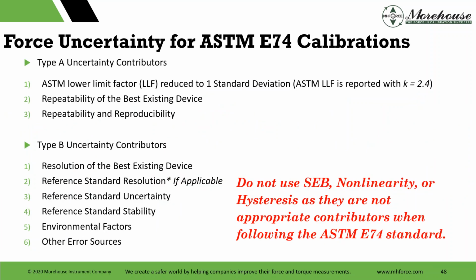Anyway, going on, we had that paper on uncertainty, and typically when we're looking at uncertainty for force, it doesn't end with what I just showed you of the 0.002. You have to get that device, you're accredited, and now you have to do more. And this is the more that most people do. You're going to take your type A, which is going to be the ASTM lower limit factor, reduced to 1 standard deviation. You're going to do a repeatability study of the best existing device. You may do a repeatability and reproducibility between technicians.